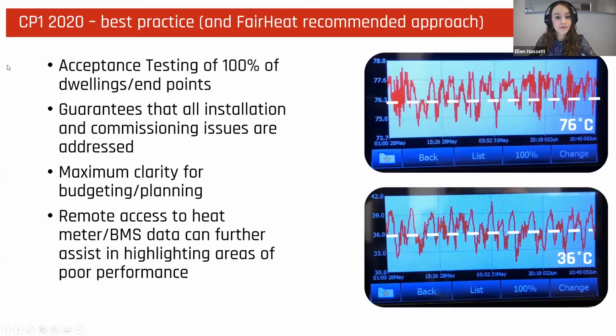On to you, Freddie. Cool, thank you, Ellen. As Gareth said, we're completely thrilled and proud that acceptance testing has been included within CP1 2020 as a minimum requirement. Although our recommended approach is to take this step one further, and basically our approach is to undertake the CP1 best practice. The best practice outlines that acceptance testing should be carried out over 100% of dwellings and endpoints. And this ensures that correct service levels and design return temperatures can be achieved across the network. This way, the developer and client has the complete confidence that all installation and commissioning issues are addressed and rectified pre-occupation.